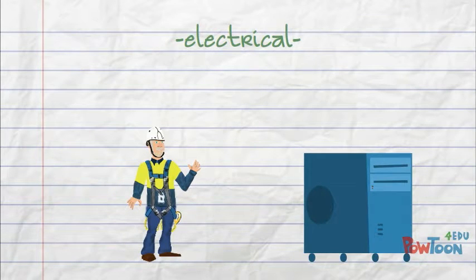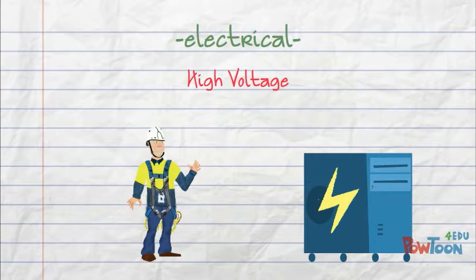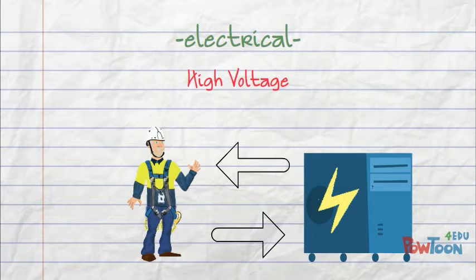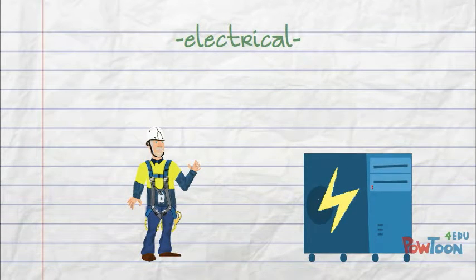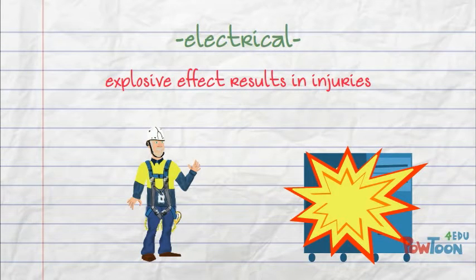Technicians can also be required to operate and maintain equipment that falls under the definition of high voltage. Operation of high voltage equipment comes with its own unique hazards, in that technicians don't necessarily have to come into direct or indirect contact with equipment to suffer adverse physical effects of a high voltage incident. Statistics have shown that it is usually the catastrophic explosive effect resulting from equipment or system failure that represents the greatest risk to high voltage workers' health and safety. Arc flash burns sustained by workers represent a significant number of serious injuries and deaths within the industry.